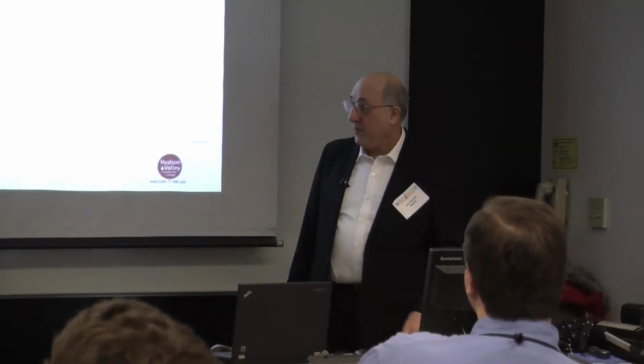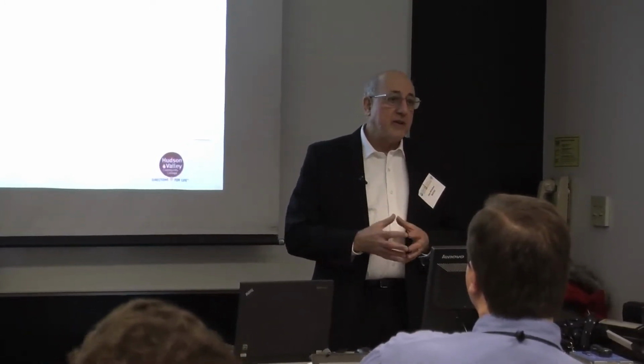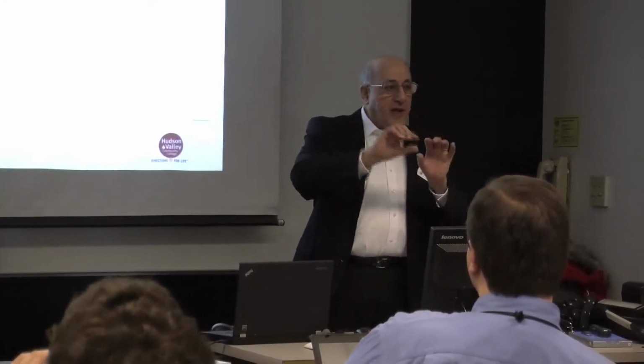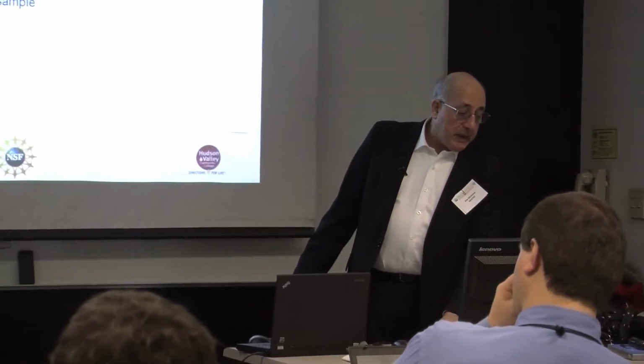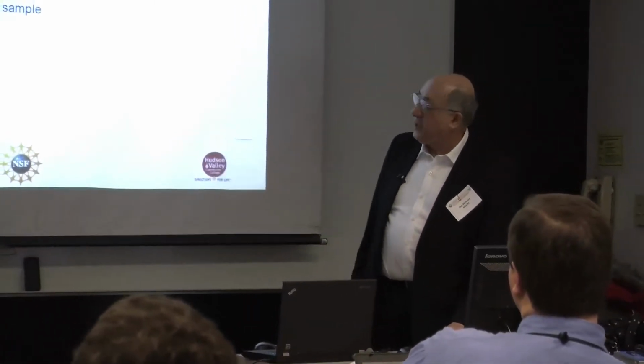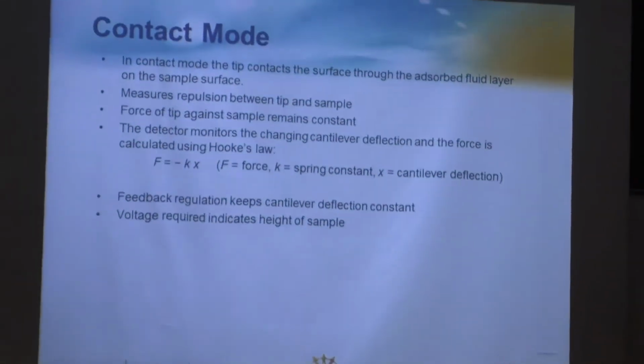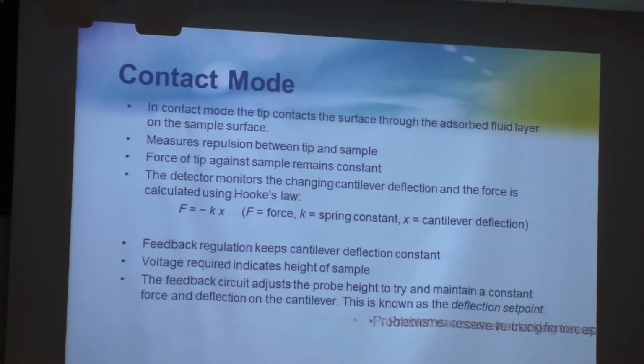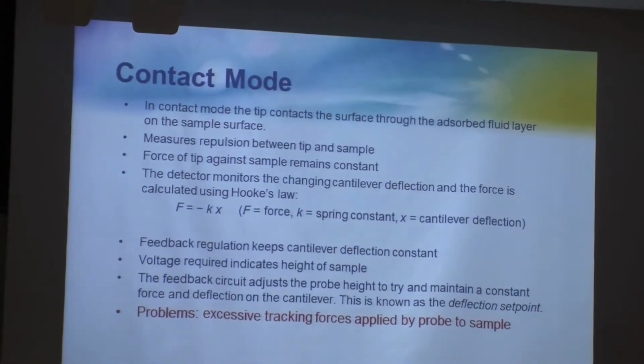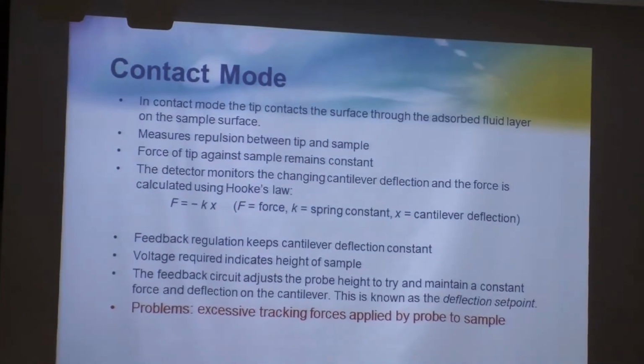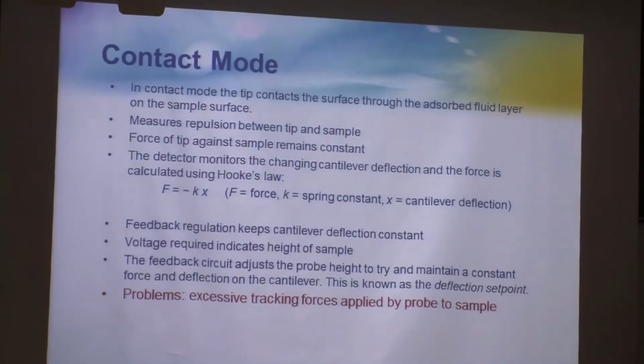We use a very simple control system, a PID. Who is familiar with controllers? This is a type of feedback control system called PID, and it is very important. If, for example, the tip is too far away, the controller will move it closer, and throughout the process the distance will stay the same. We can measure the voltage between the sample and the tip. It is very important to track force and distance at all times, but this makes the system a little more complicated.